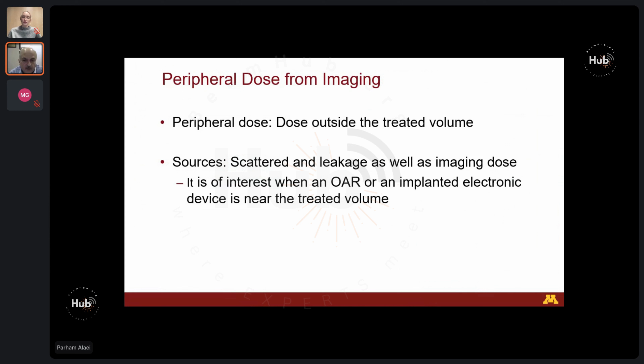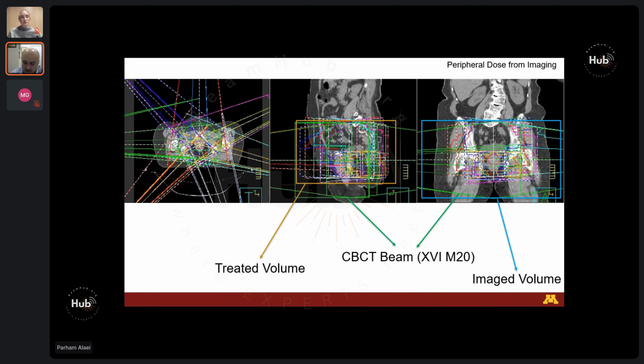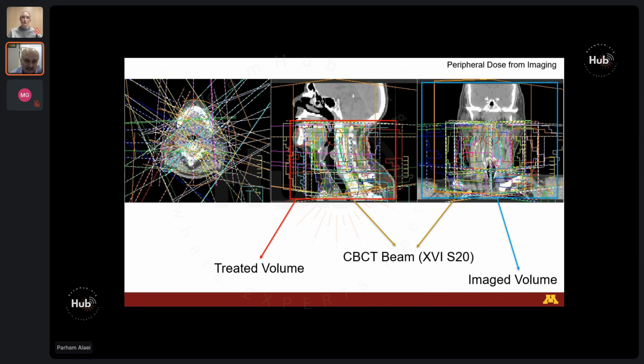Again, just an example of that: this is a 7-field IMRT, and the treated volume is the yellow color. Then you put a cone beam CT on it, and the image volume is going to be this blue line. So the treated volume is the pelvis, and the image volume includes the groin area. Another example, head and neck, a 9-field IMRT. The treated volume is the red box, the image volume is the blue box. The treated volume is head and neck, but the image volume includes most of the brain and the eyes and optic nerves and all that. So the image volume is almost always larger than the treated volume on a C-arm linac because of the fixed blade settings and cassette size.